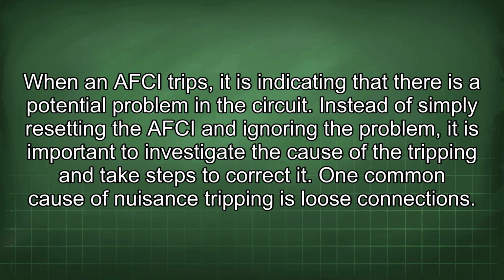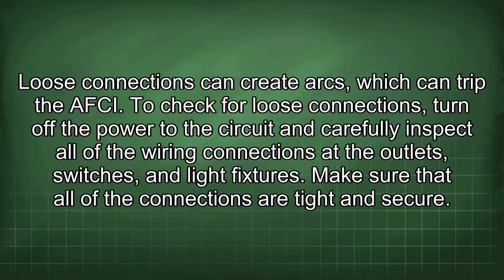When an AFCI trips, it is indicating that there is a potential problem in the circuit. Instead of simply resetting the AFCI and ignoring the problem, it is important to investigate the cause of the tripping and take steps to correct it. One common cause of nuisance tripping is loose connections. Loose connections can create arcs, which can trip the AFCI.